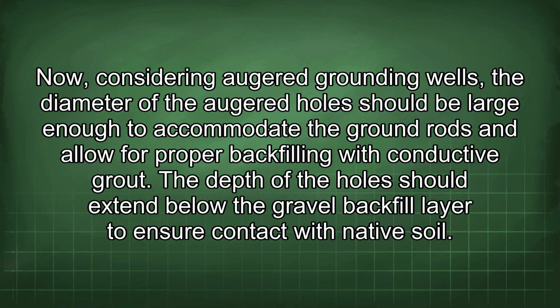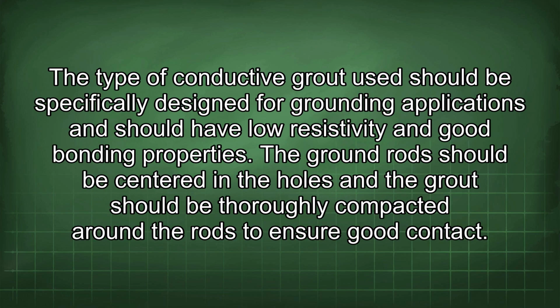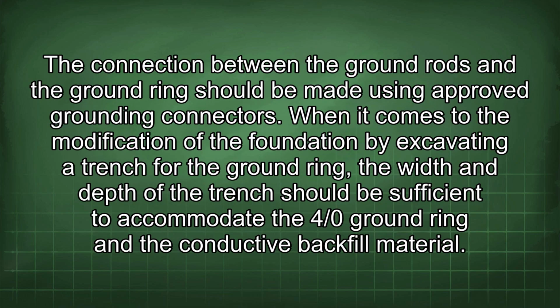Now, considering augered grounding wells, the diameter of the augered hole should be large enough to accommodate the ground rods and allow for proper backfilling with conductive grout. The depth of the hole should extend below the gravel backfill layer to ensure contact with native soil. The type of conductive grout used should be specifically designed for grounding applications and should have low resistivity and good bonding properties. The ground rods should be centered in the holes and the grout should be thoroughly compacted around the rods to ensure good contact. The connection between the ground rods and the ground ring should be made using approved grounding connectors.